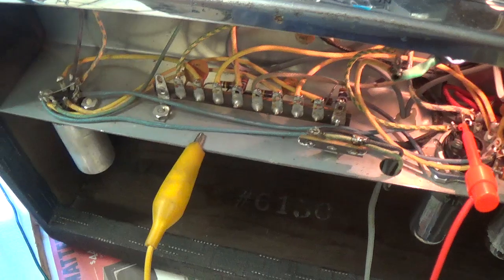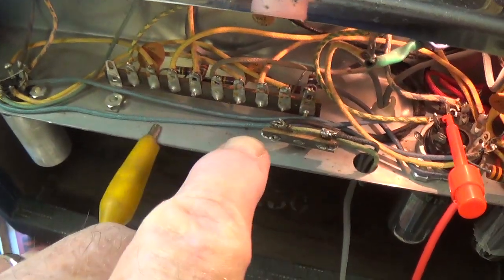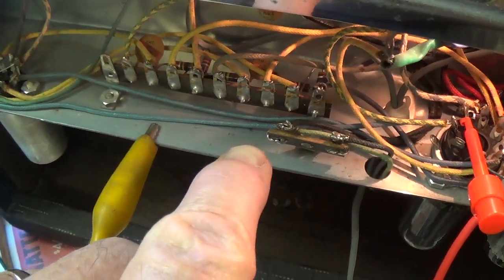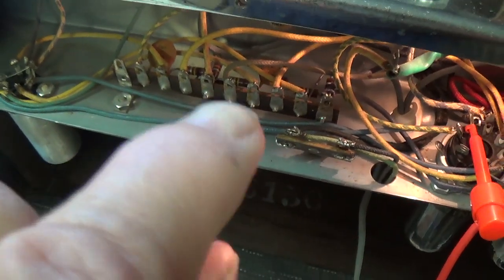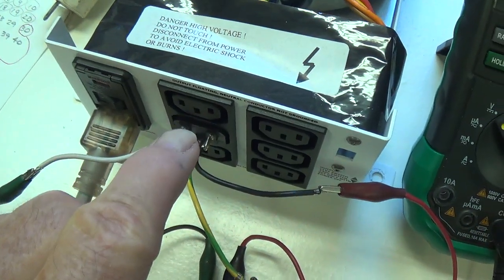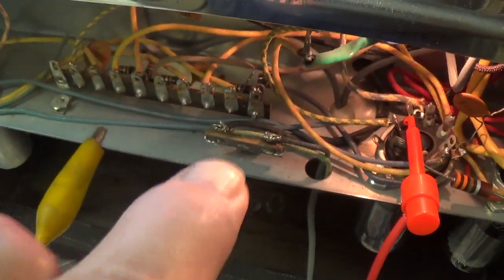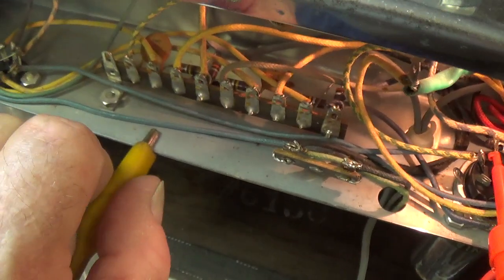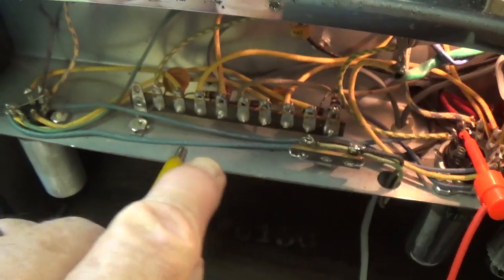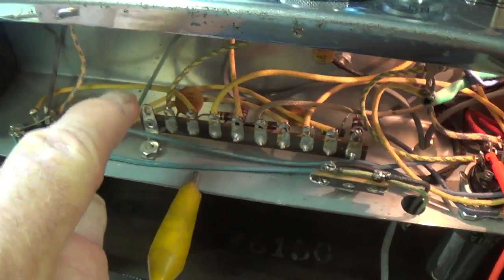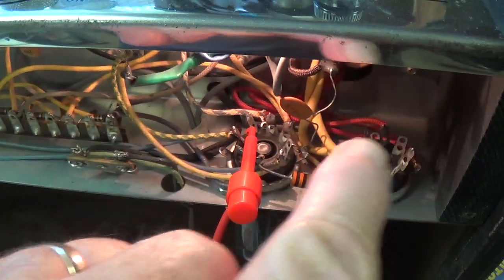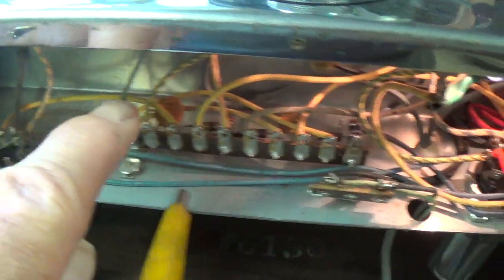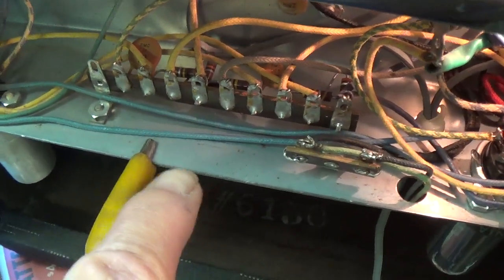So as you can see, there is a huge difference between plugging in the electronic device with a 3-wire chassis grounding cord into your isolation transformer or using a 2-wire cord. With the 3-wire cord, the ground reference is the chassis, and you cannot connect your oscilloscope ground lead anywhere in here without destroying the probe or the scope, except for the chassis itself.